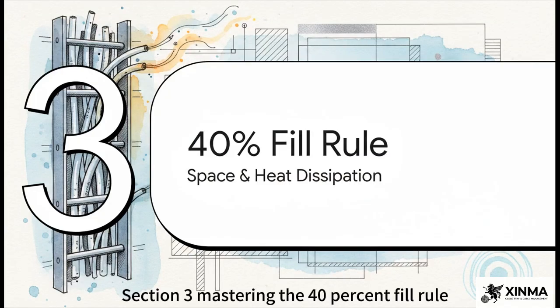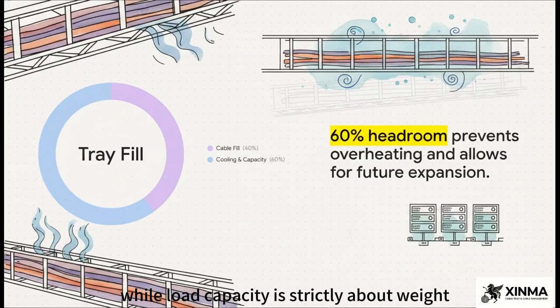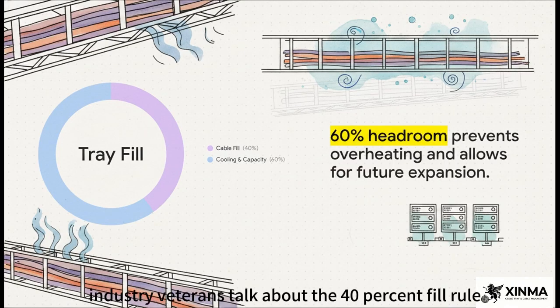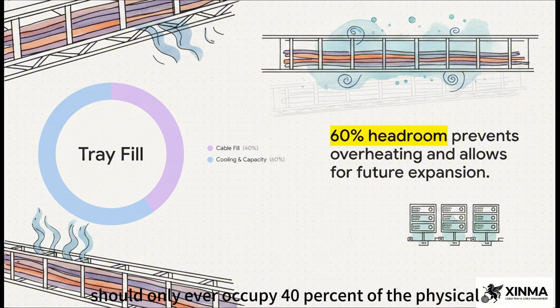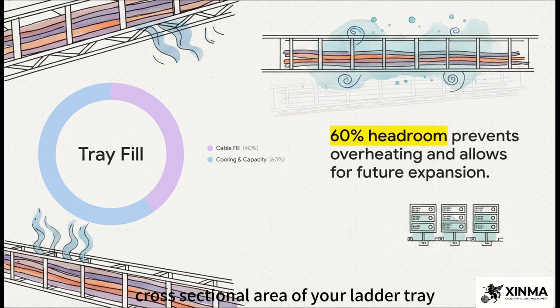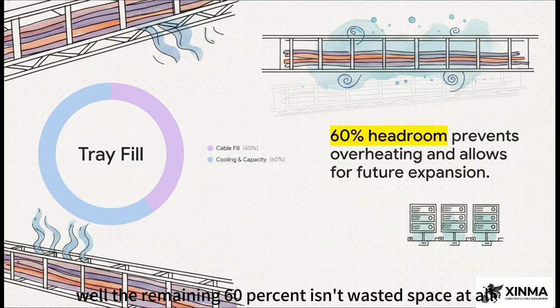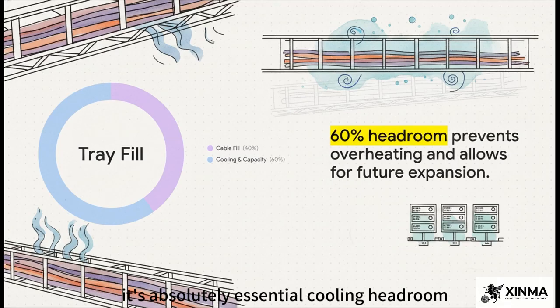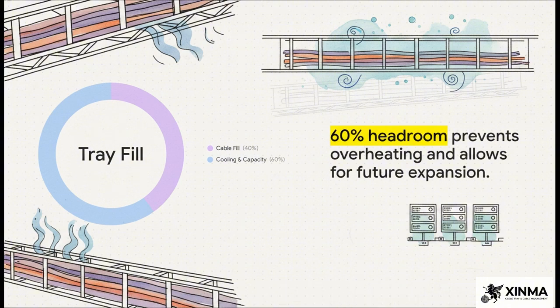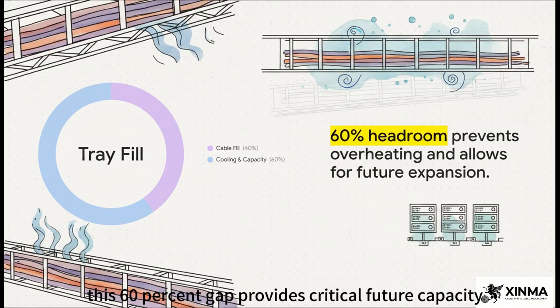Section 3: Mastering the 40% fill rule. While load capacity is strictly about weight, tray width is all about physical space. You're going to constantly hear industry veterans talk about the 40% fill rule. What that actually means is your cables should only ever occupy 40% of the physical cross-sectional area of your ladder tray. But why? Well, the remaining 60% isn't wasted space at all - it's absolutely essential cooling headroom. Like we learned with that 12% derating drop earlier, cables desperately need room to breathe to operate efficiently. Think of it like leaving enough space in an oven for the hot air to actually circulate. Furthermore, this 60% gap provides critical future capacity.